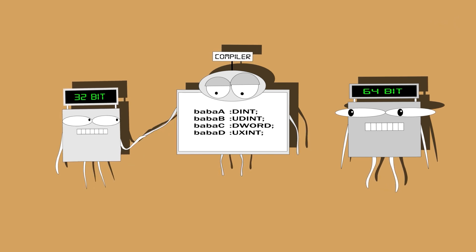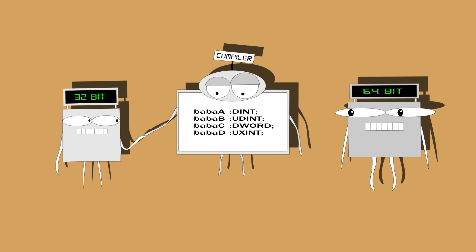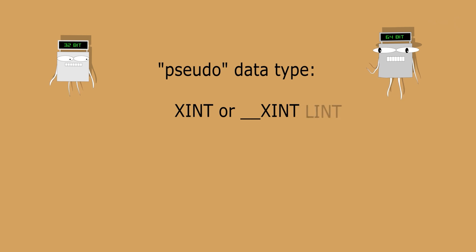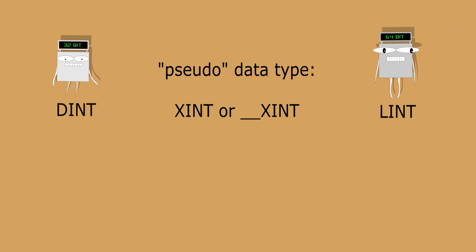You can also use the type conversion operators for variables of these data types. The following pseudo data types are available: XINT, or __XINT, is converted to the standard data type LINT on 64-bit platforms and to the standard data type DINT on 32-bit platforms.